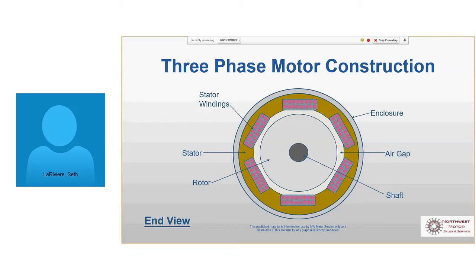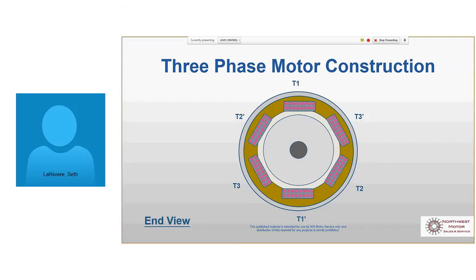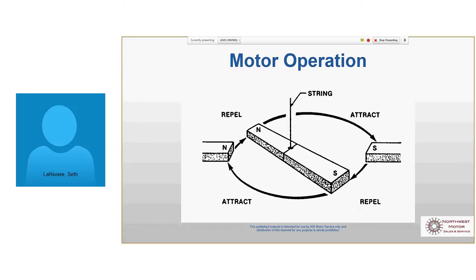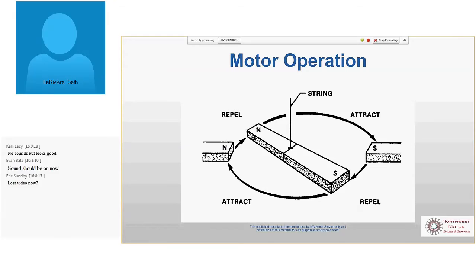All right, so components inside the motor are the stator windings, the stator, the rotor, of course, the outside enclosure, the air gap between the rotor and the stator, and of course the motor shaft. If we look at the corresponding poles, there are two poles, positive and negative, for every one of these, so they're 180 degrees opposed. We're going to show you how that works. It's basically like a magnet on a string: north and south attract, north and north repel. That's what's happening inside that motor: we're switching between the two poles. So half the time the motor is pulling towards the next pole, pushing away from the last one. That's how we're getting rotation in the motor.